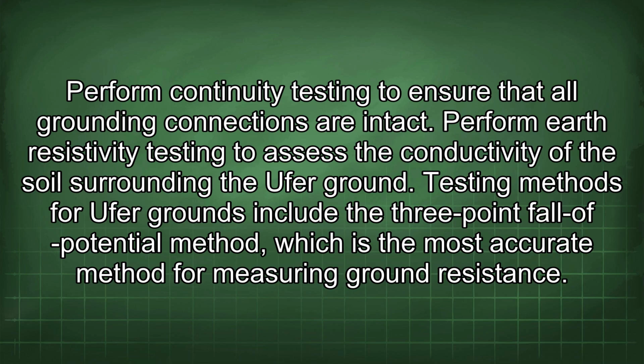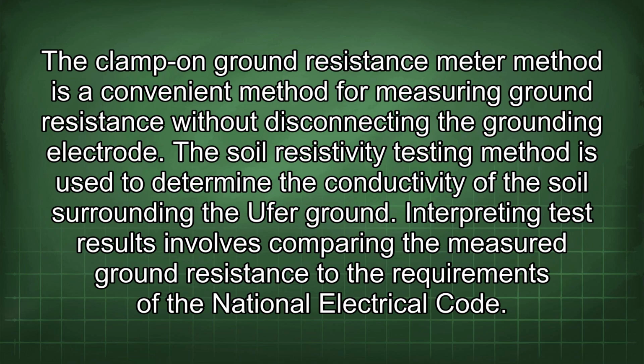Testing methods for Ufer grounds include the 3-point fall of potential method, which is the most accurate method for measuring ground resistance. The clamp-on ground resistance meter method is a convenient method for measuring ground resistance without disconnecting the grounding electrode. The soil resistivity testing method is used to determine the conductivity of the soil surrounding the Ufer ground.